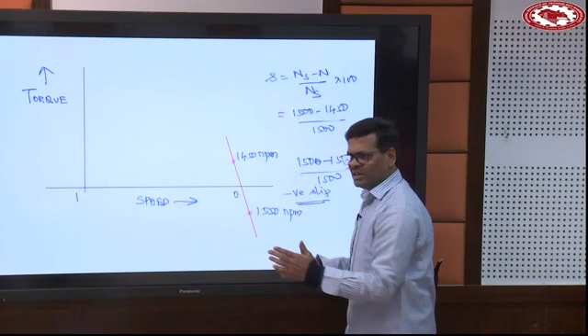So it is called the narrow speed range induction generator. What it means is, if the wind speed is such that the turbine speed after the gear is between 1500 and 1550 rpm, then only you will have the generation. Is that understood? Right? Suppose 1500 rpm corresponds to 10 meter per second wind and 1550 corresponds to 12 meter per second. So if the wind speed is between 10 and 12 meter per second, then only you will have the generation. So it is like a narrow speed range induction generator.